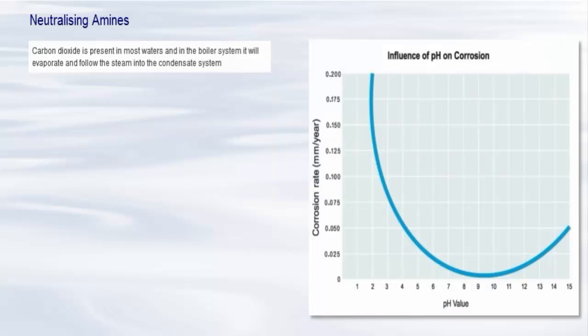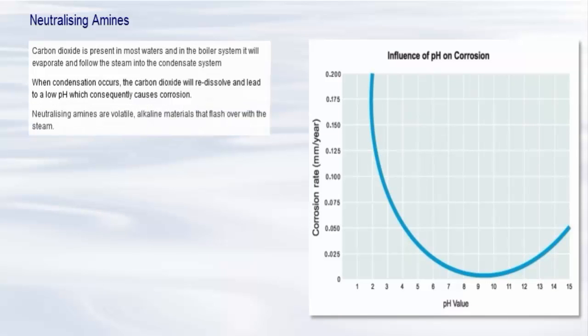Carbon dioxide is present in most waters and in the boiler system it will evaporate and follow the steam into the condensate system. When condensation occurs, the carbon dioxide will redissolve and lead to a low pH which consequently causes corrosion. Neutralizing amines are volatile, alkaline materials that flash over with the steam. They combine with the condensate water to elevate pH and provide corrosion protection.